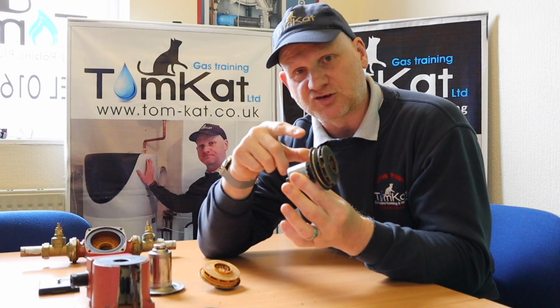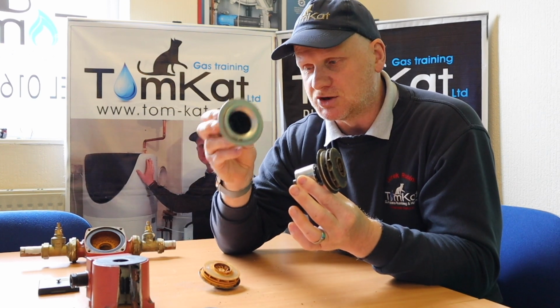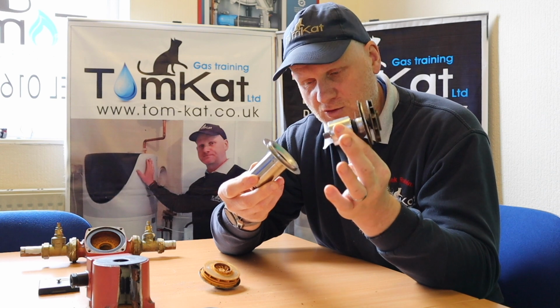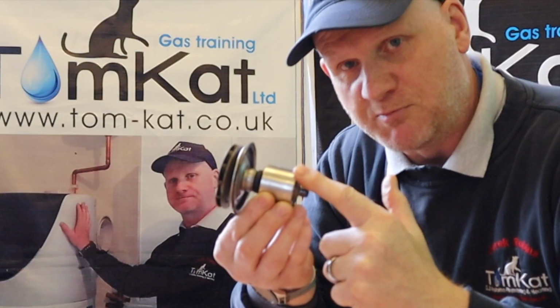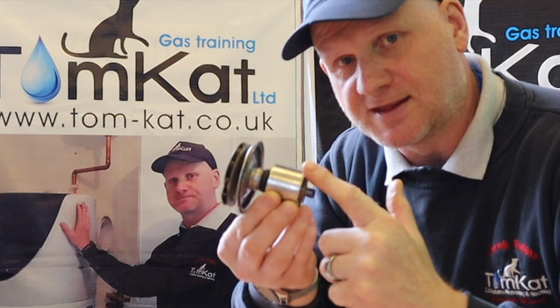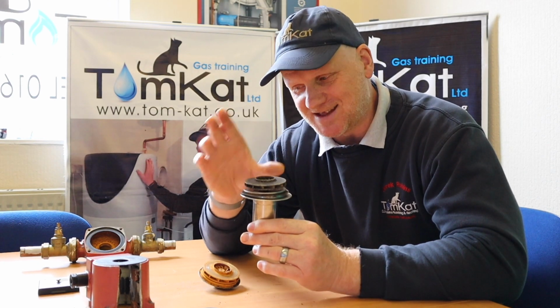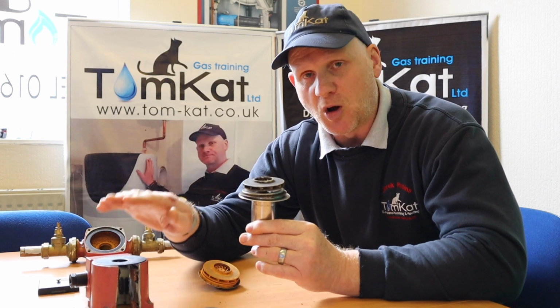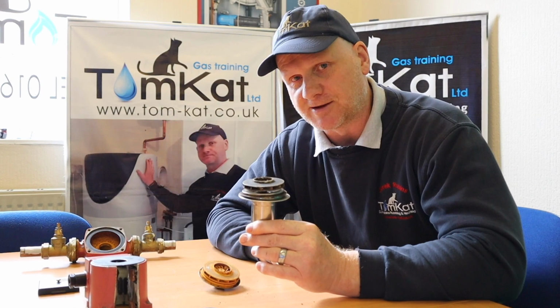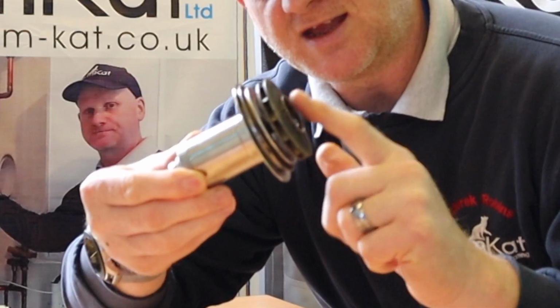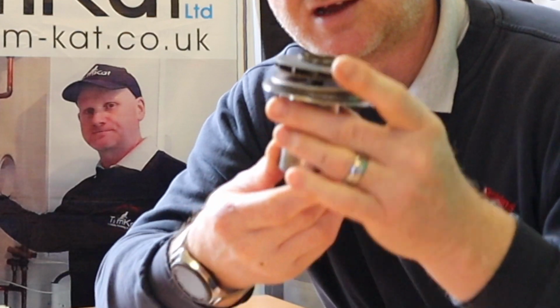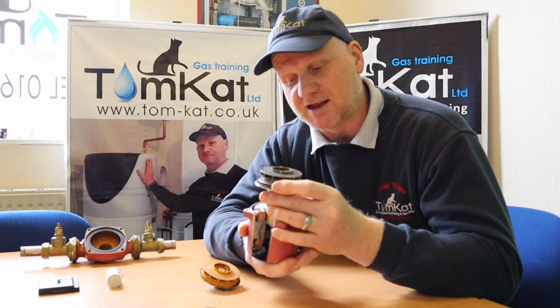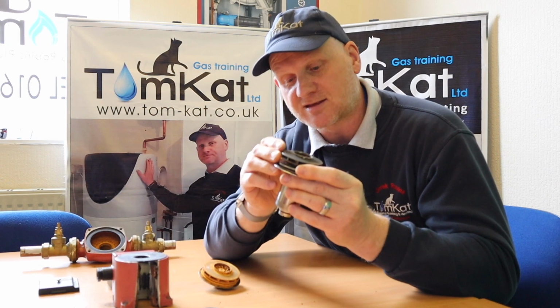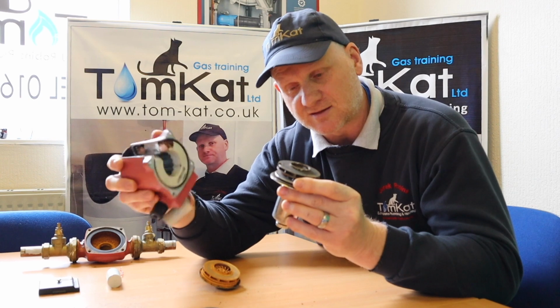Now, it needs to be kept separate from the head, because there's water in there, and this is what this little bell housing does. So the actual rotor sits inside the bell housing, and the bearings inside here are lubricated by the central heating water. The pump, believe it or not, even though the water is 82 degrees, or could be 82 degrees, is cooled by the central heating water. Okay? So you can see the impeller attached to the shaft, you can see the bell housing, and the bell housing then would sit in there, and that makes this completely watertight from this, so water can't get into the motor.